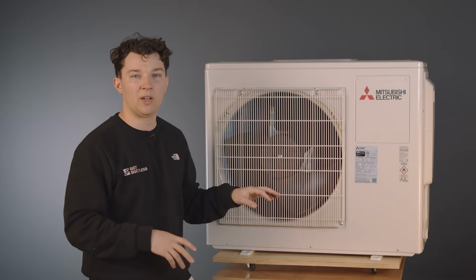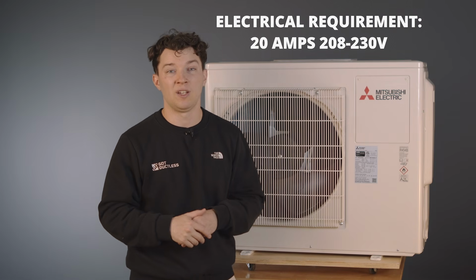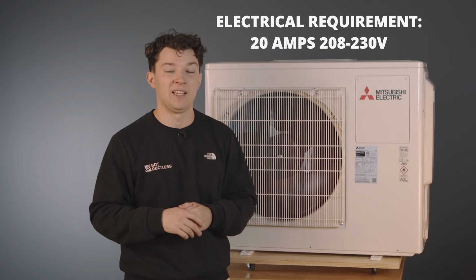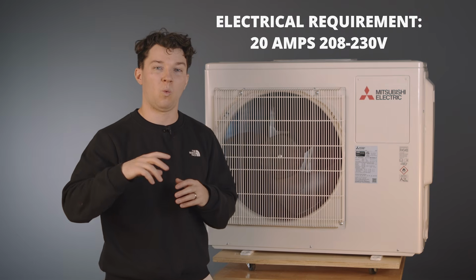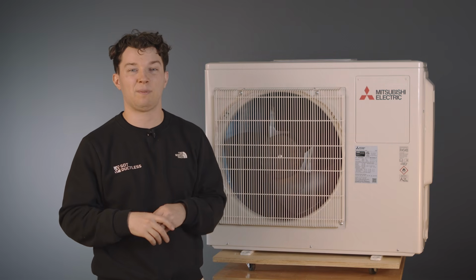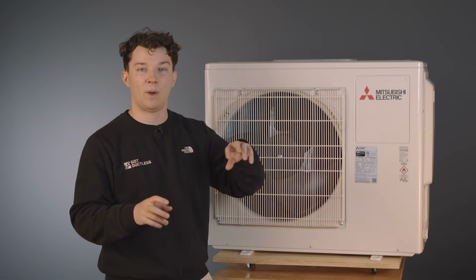Now this outdoor unit requires 20 amp service, 2-pole, of course, 230, and so when you're running your wire, your high voltage line from your breaker box to your disconnect box, and from your disconnect box using a whip to this outdoor unit, just account for that 20 amp 2-pole service.